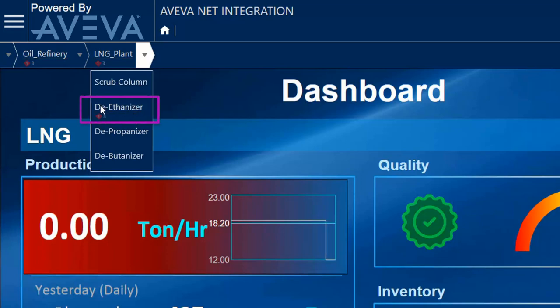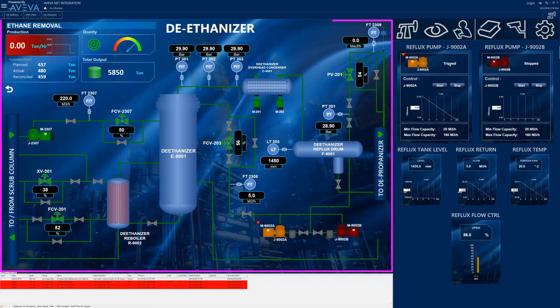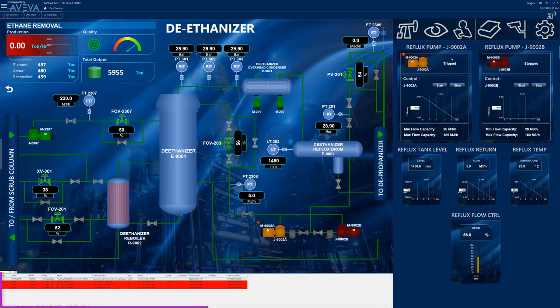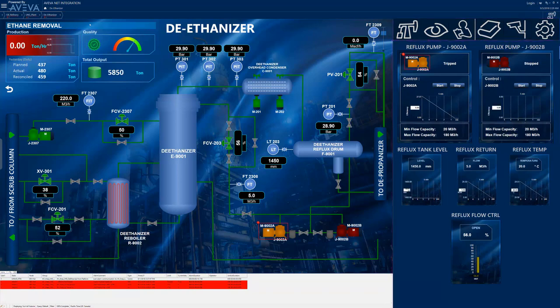The deethanizer is where the problem is, so the operator selects that area. The deethanizer detail screen is divided into four areas: the stylized P&ID, the alarm and events display at the bottom, and on the right, the integration menu at the top and the equipment faceplates. The operator can see that the deethanizer is at zero production and can see an alarm indicator surrounding the reflux pump J9002A in both the stylized P&ID and the pump's faceplate.